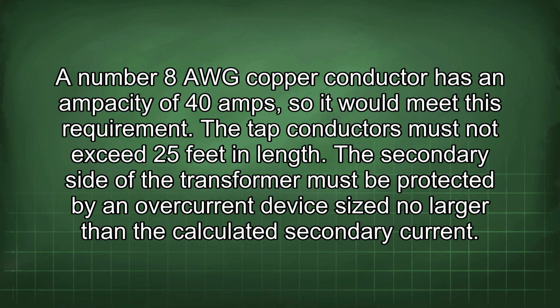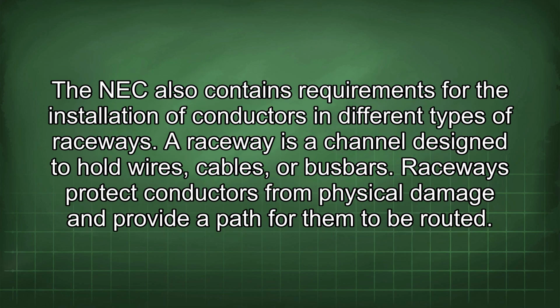A number 8 AWG copper conductor has an ampacity of 40 amps, so it would meet this requirement. The tap conductors must not exceed 25 feet in length. The secondary side of the transformer must be protected by an overcurrent device size no larger than the calculated secondary current.